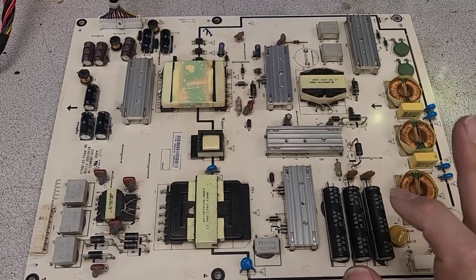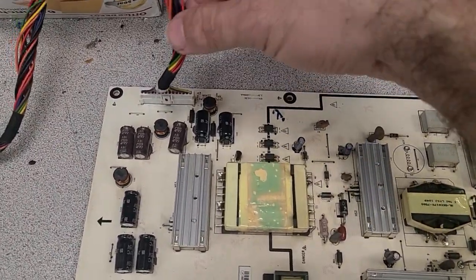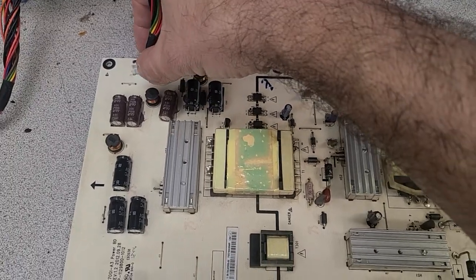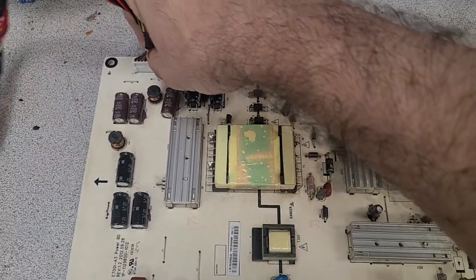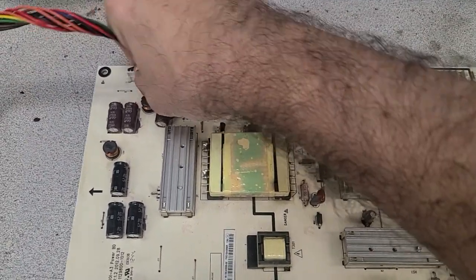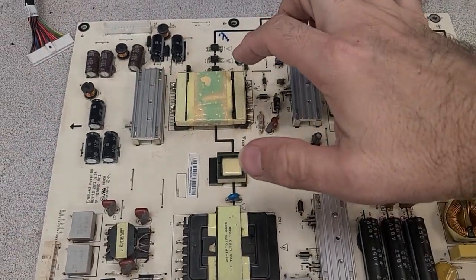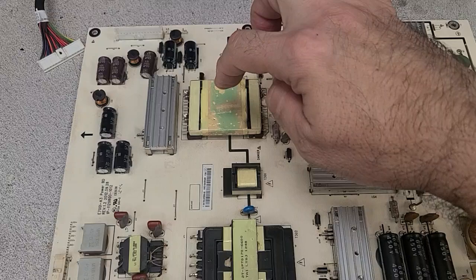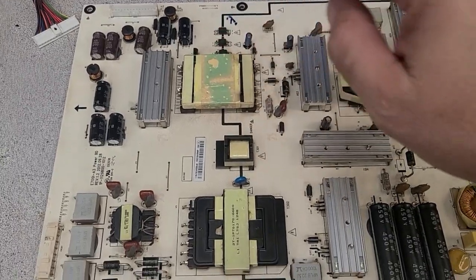That's the one very common thing you need to check, and the other is the output of those secondary circuits. Usually if you have stable voltage for one secondary circuit, like the 12 volts in this case, the others will be stable too, because they all come from the same transformer. If one has a problem, it affects all the others.